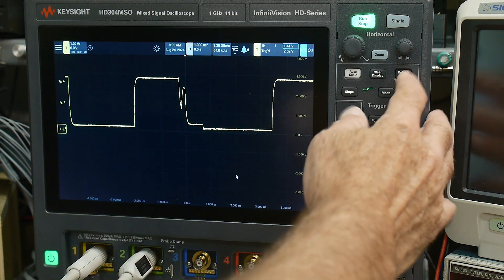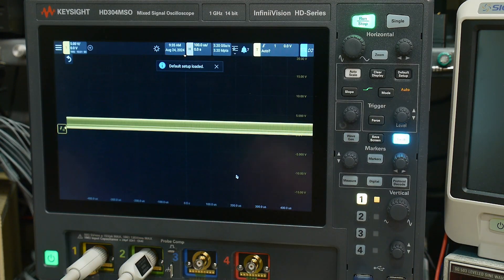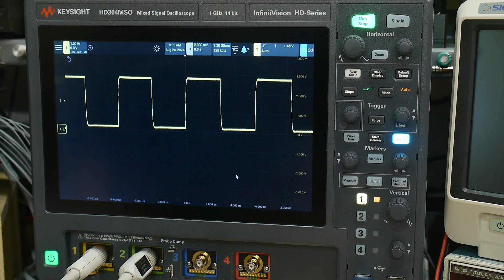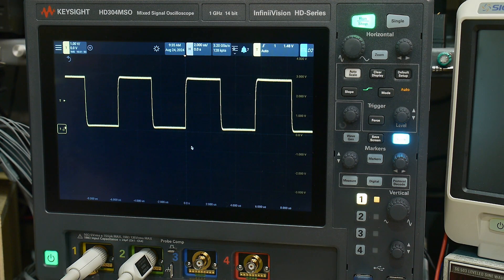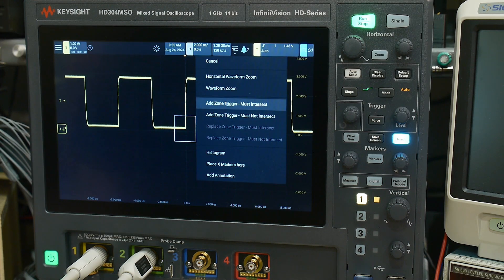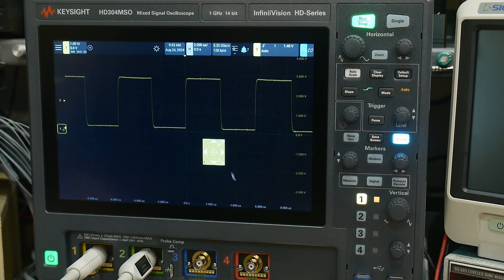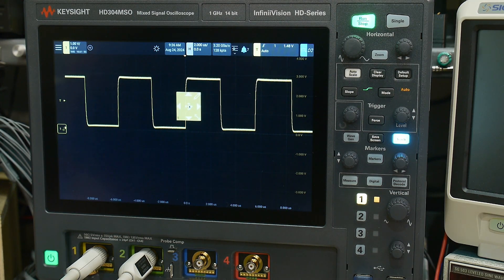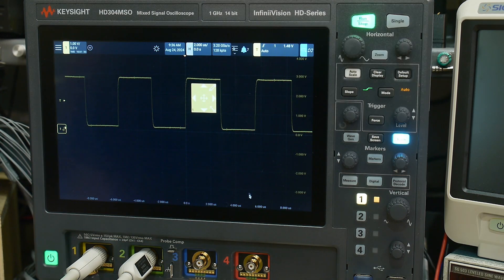Let's go back to default setup and make it bigger again — set 50 percent, zoom in again. Now what this scope has is zone triggering. What you do is just draw a box. I'm going to draw a box and say it must intersect, so it creates this zone and the waveform must go through that box for it to trigger. If I move that box over here you can see that it stopped triggering, but if I put it here it will trigger on it.